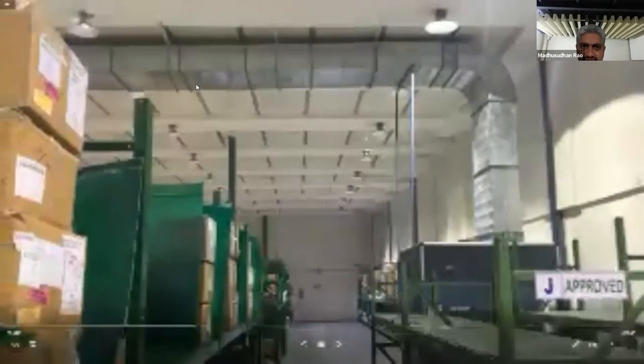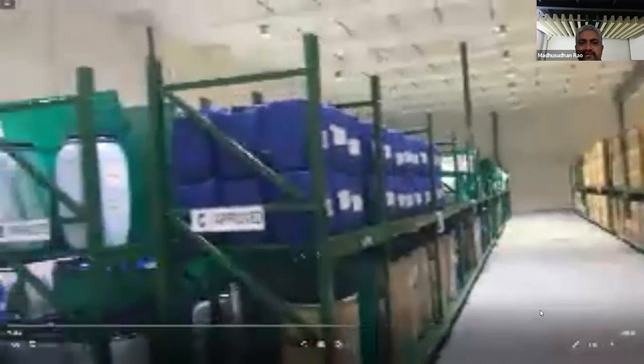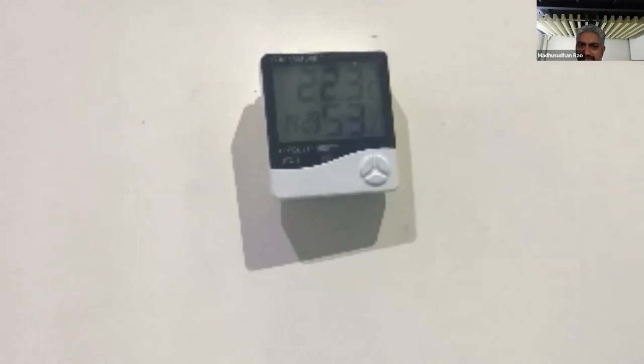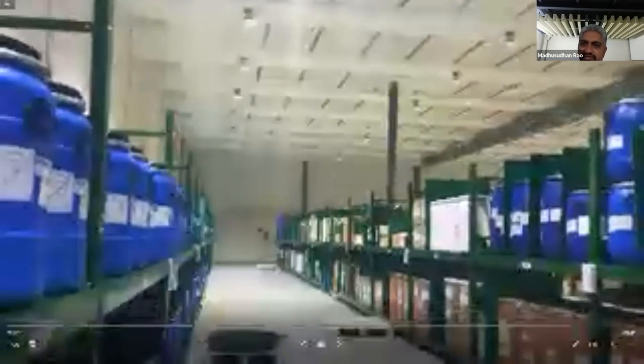So of course, there is an air system to maintain humidity. As I mentioned, this space needs to be maintained 24/7, 365 days, at 22 plus or minus 1, because this is a finished goods warehouse for a pharma company. There are US FDA approved audits that are happening every quarter to see that there's no temperature variation across. That was the other reason why they chose to have radiant cooling, apart from the energy savings, because it allowed them to have uniform temperature across.